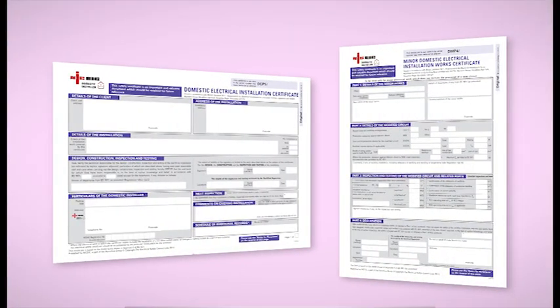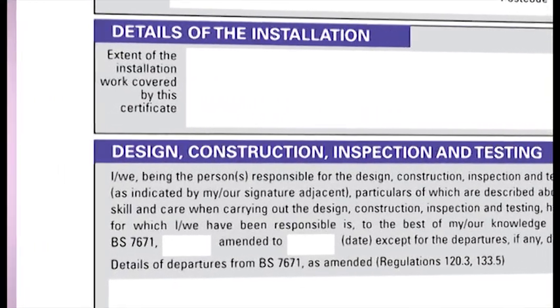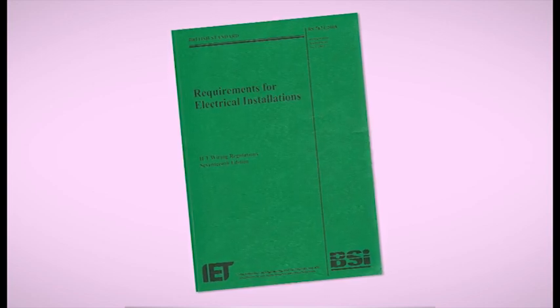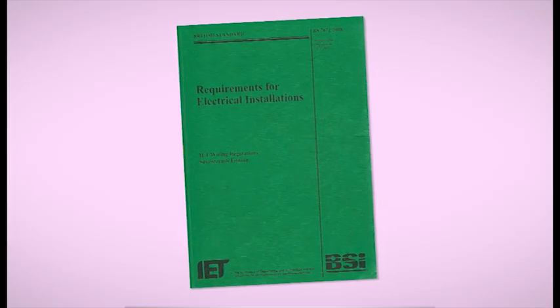Dave, we've discussed some of the requirements of the regs, but actually there's a good common sense reason for issuing certificates and report forms, and that is that these bits of paper are often the only evidence a contractor has that he's been on site, that his work was left in a safe condition and complied with the wiring regs. It is important to understand what issuing a certificate or report form actually means. A certificate is issued to confirm that the work undertaken within its scope has been designed, constructed, inspected, tested and verified in accordance with the current national standard for the safety of electrical installations, BS 7671, the wiring regulations.